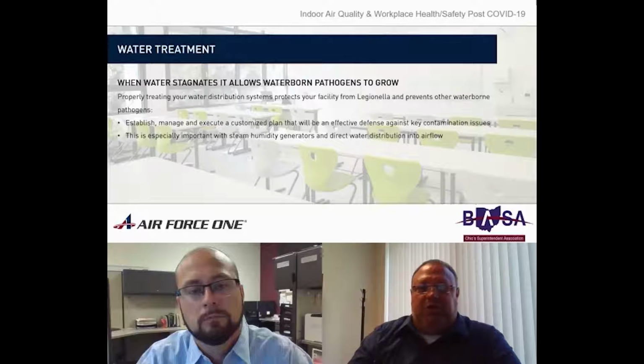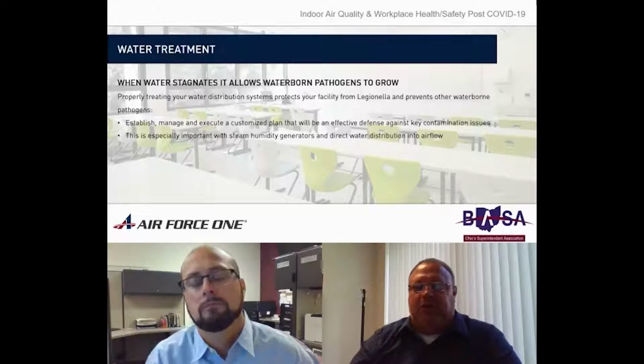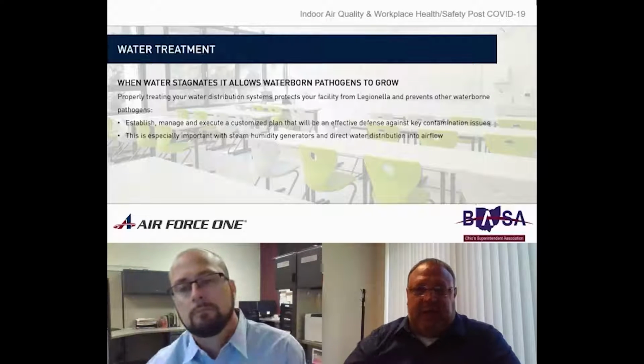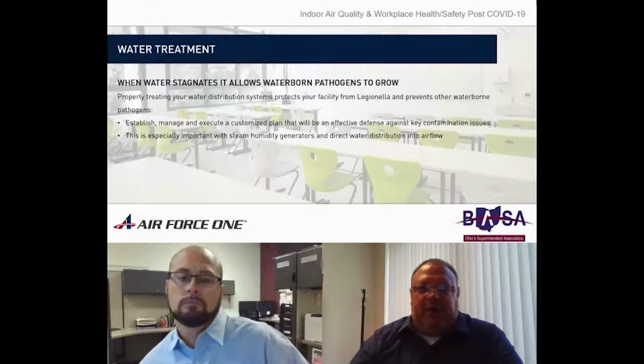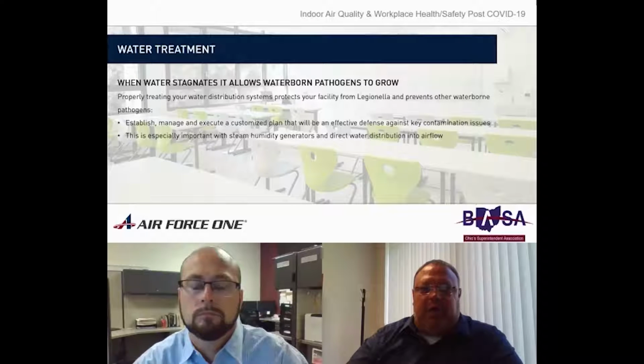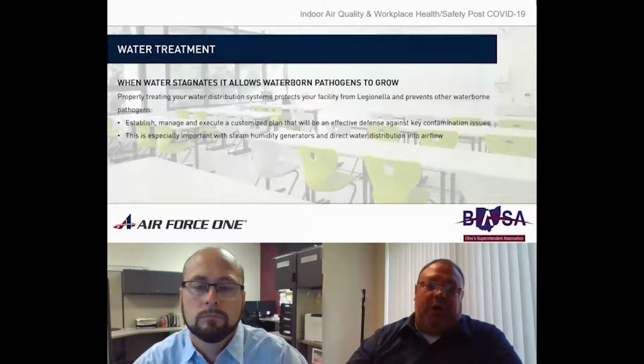The other part that I think people really don't think about is as that water quality goes down, you still have steam coming off the tower, and people say, well, we don't have kids or we don't have people standing right by the tower, so why is it an issue? Where your tower sits, if it's upstream of prevailing wind, all that steam that's coming off the tower, whether you can see it or not based on dew point, goes over the school, and then all of your equipment that's bringing in outside air is now bringing that low quality, moisture-ridden, sometimes bacteria and mold-ridden air back into the space, which causes problems with your cooling coils and, of course, lowers IAQ inside the building. Very important to make sure that that's treated.